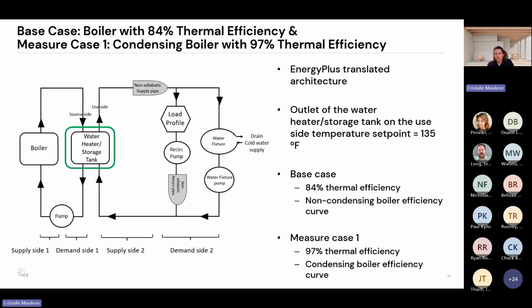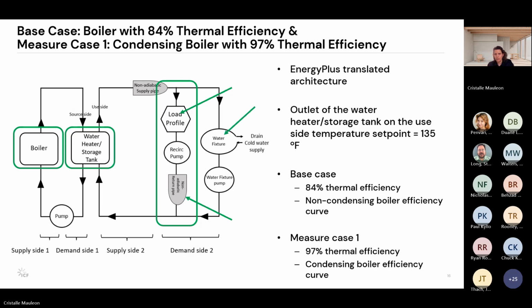Both systems include a storage tank with a temperature set point of 135 degrees, and the boiler capacity is auto-sized by Energy Plus. The recirculation loop includes non-adiabatic piping to simulate heat loss, and a load profile object schedules flow independently from the demand. Unlike measure cases 2, 3, and 4, which were the heat pumps, this configuration didn't require any heat exchangers between the heat pump water and the potable water, and so the model is able to model the flow dynamics without any needed simplification.